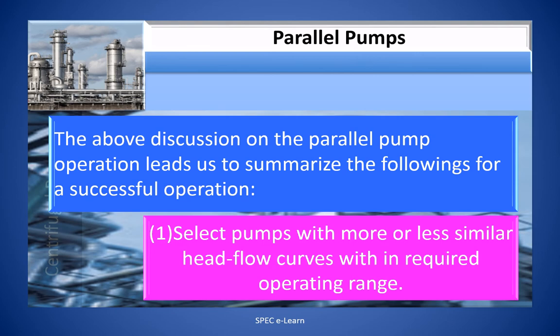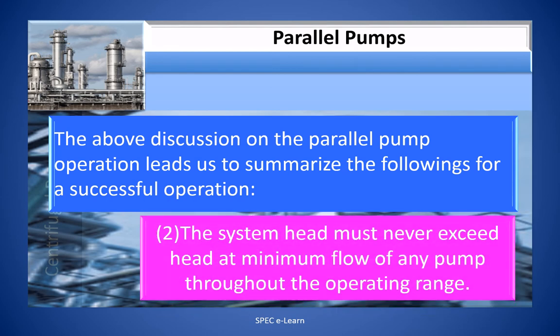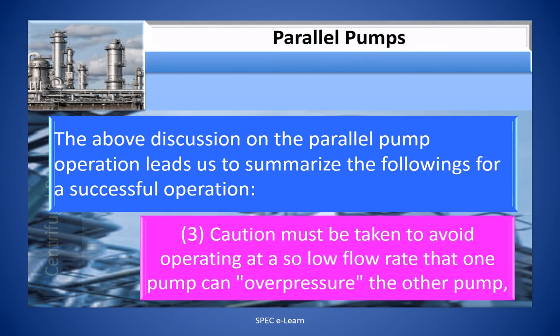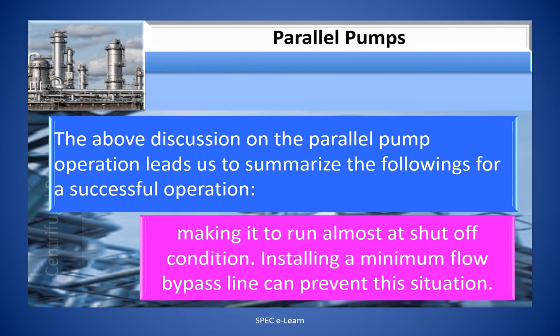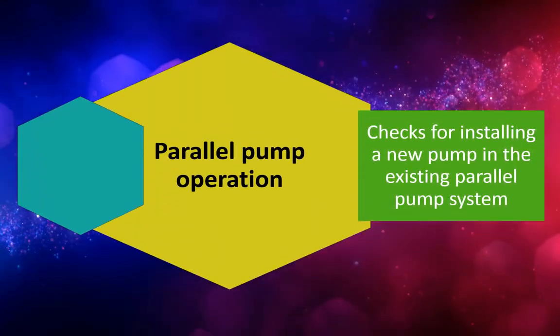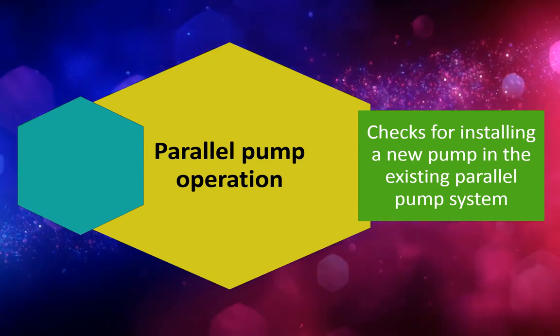The above discussion on parallel pump operation leads us to summarize the following for a successful operation. 1. Select pumps with more or less similar head flow curves within required operating range. 2. System head must never exceed head at minimum flow of any pump throughout the operating range. 3. Caution must be taken to avoid operating at so low flow rate that one pump can overpressure the other pump, making it run almost at shut-off condition. 4. Installing a minimum flow bypass line can prevent this situation. 5. Checks for installing a new pump in the existing parallel pump system.